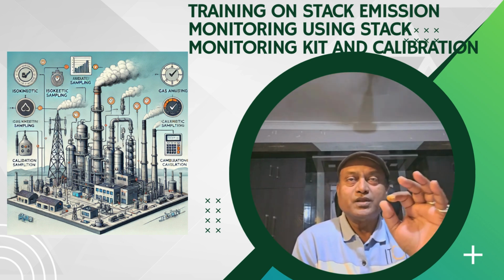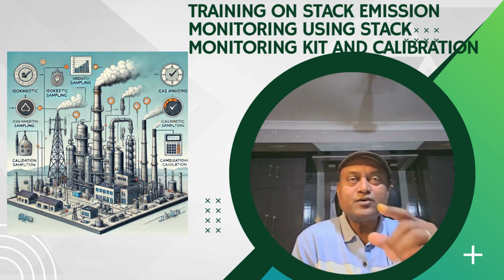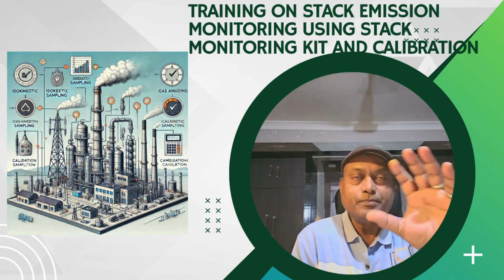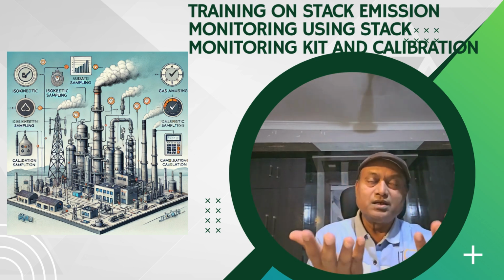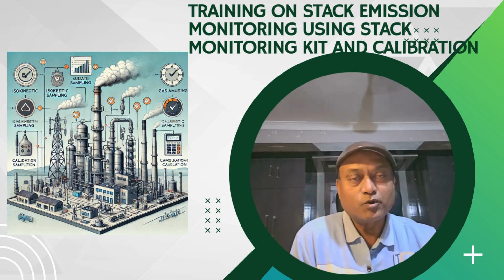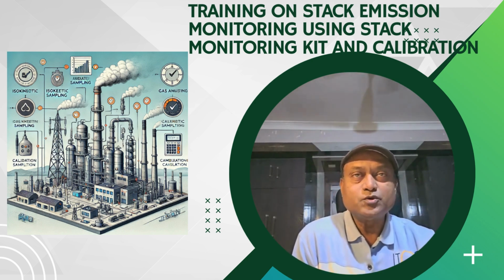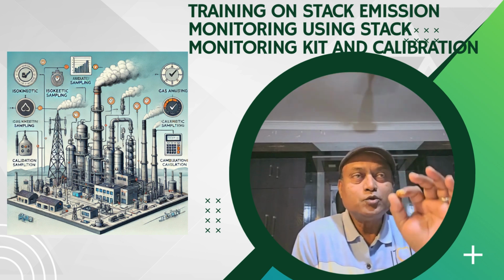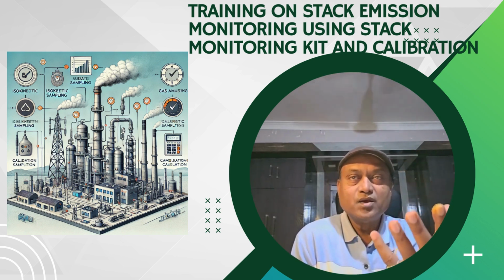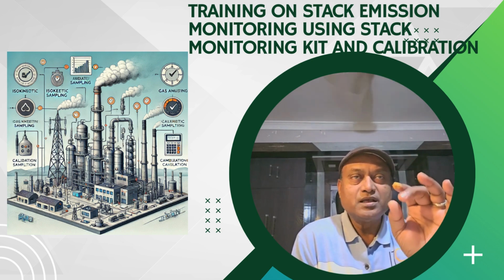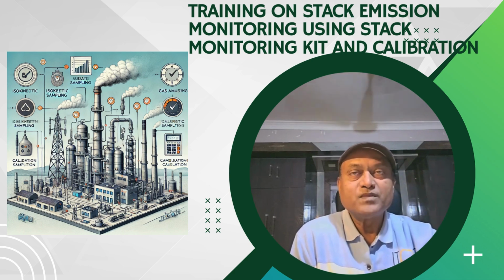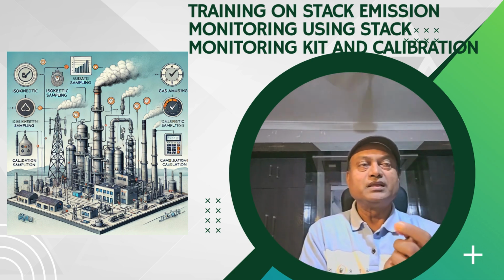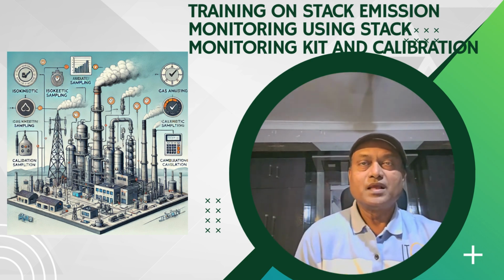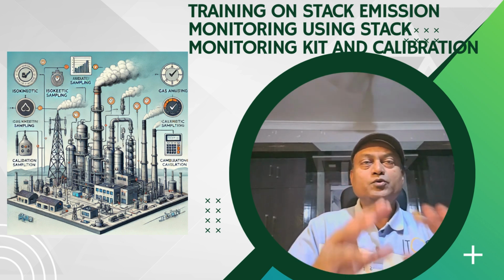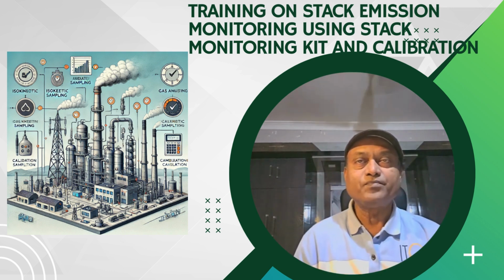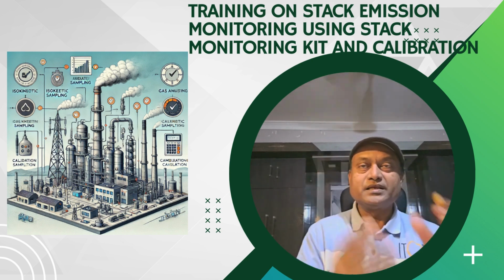Calibration procedure. Now you have to follow the zero calibration. Start with the zero gas or clean air to set the baseline. You can fix the baseline with zero gas, clean air, or inert gas. Span calibration: use the known concentration of calibration gas to test the analyzer's accuracy. Then flow meter calibration: verify the flow meter using a standard calibrator. Temperature and pressure calibration: compare the readings with a reference thermometer and pressure gauge. Particulate monitor calibration: use certified particulate matter standards.